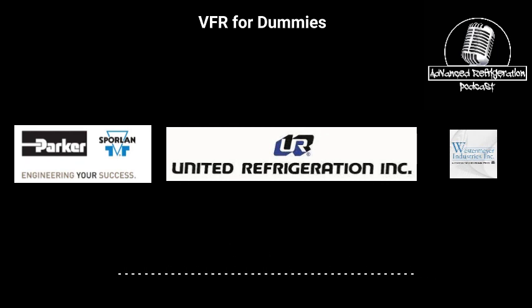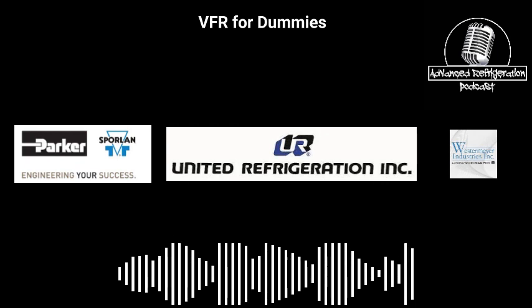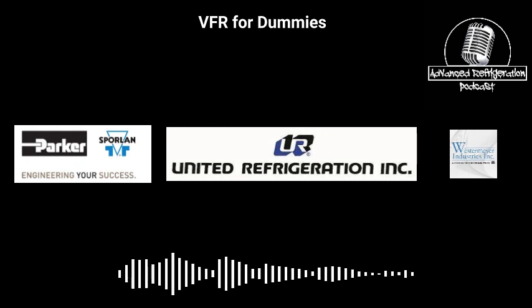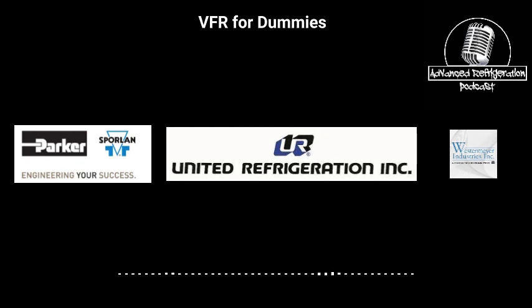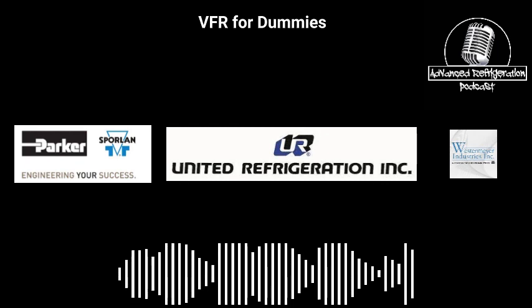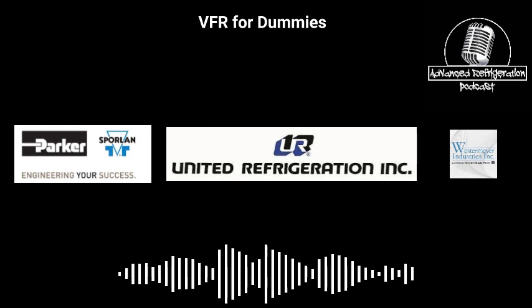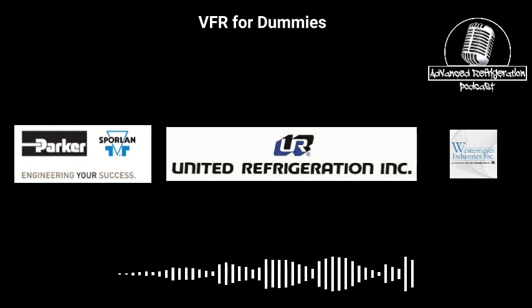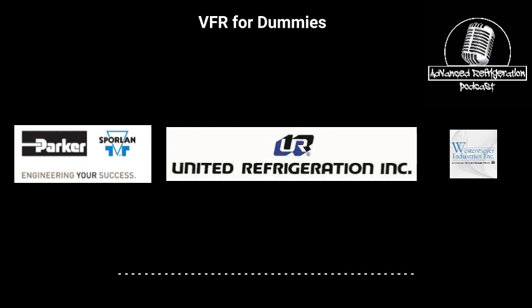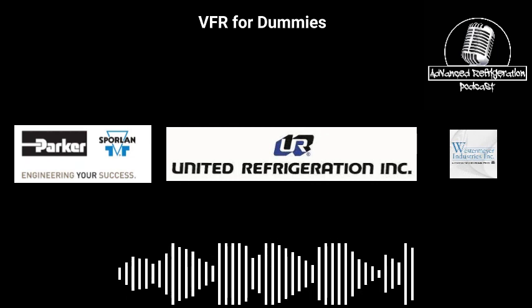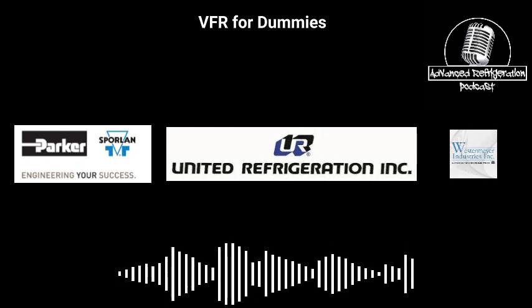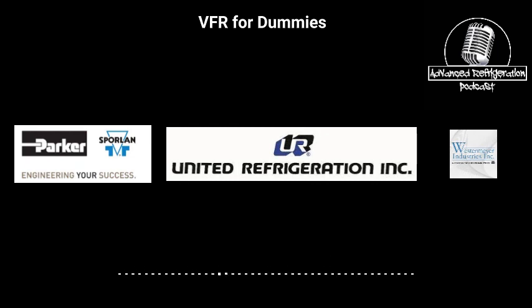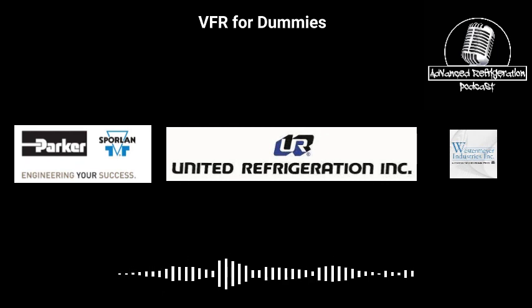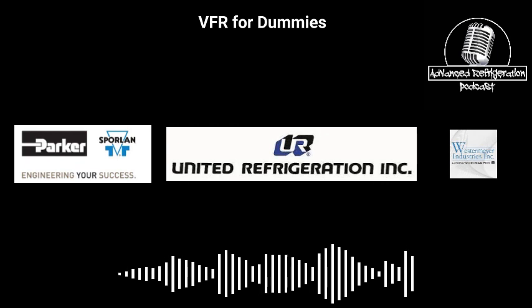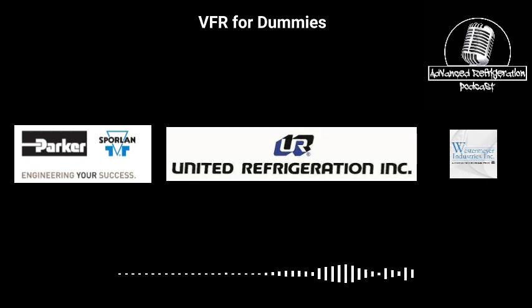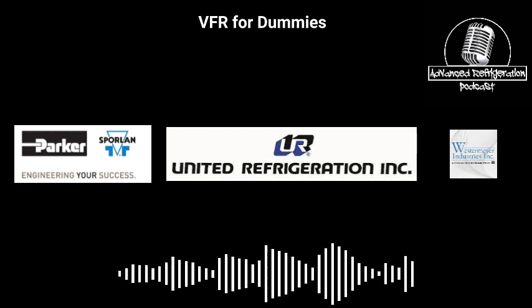Okay. There's another tube and tube. This is an older generation. On the newer generation, they have a plate and frame doing the same process as this, which is some subcooling. Gotcha. Well, the newer stuff, some of it's vapor injected, or it's vapor injected scrolls, correct? Yeah, definitely. There's no defined sequence on the Daikin heat injection. It opens, from the best I can tell, in a low load operation. I equate it to an unloader. It takes some work off the scroll.